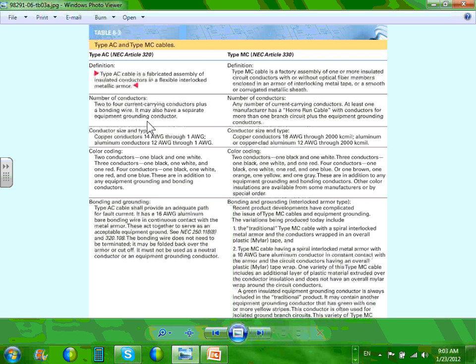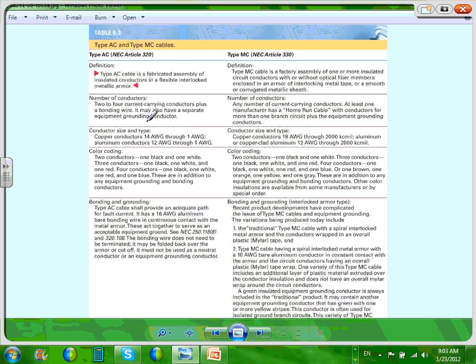126. Page 126, guys, gives you an AC/MC cable comparison: the definition and the few things that you have. I'm not going to get into all the details. I'm going to give you the most important things about this cable that you probably need to know. The article is very important, so you can see where you can use them. You can use them in almost any location. MC and AC cable are interchangeable. The major difference is that MC cable is more robust, a better cable to use, and the grounding conductor is fully insulated.